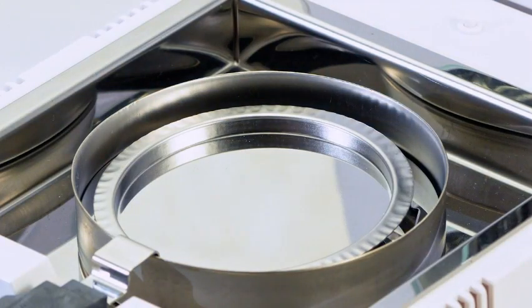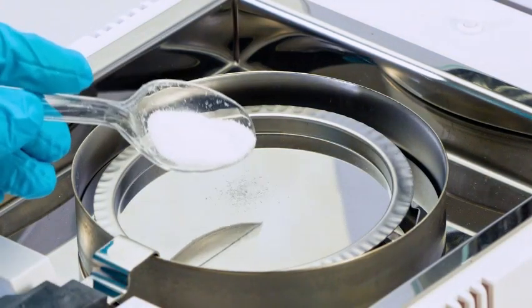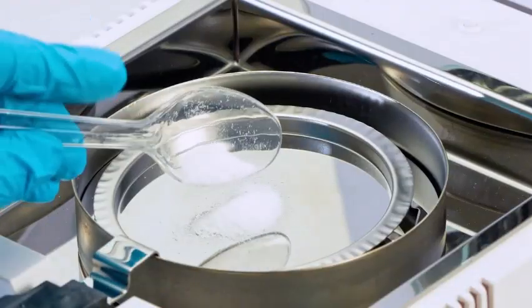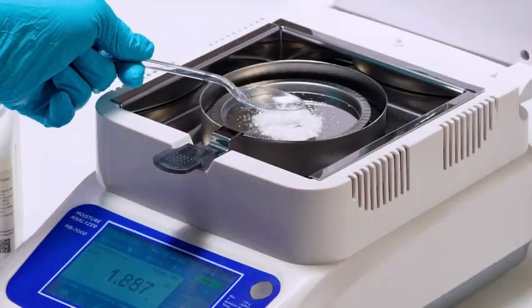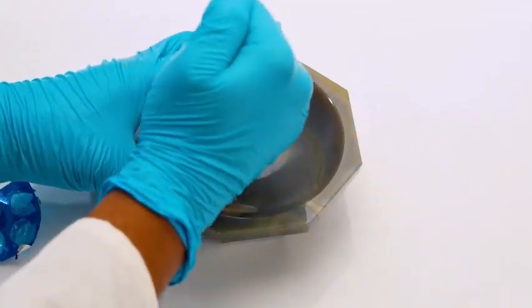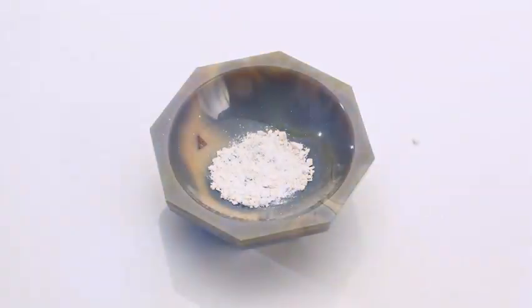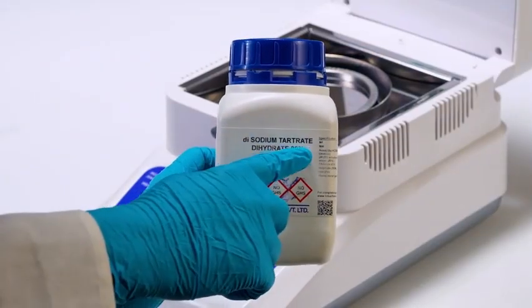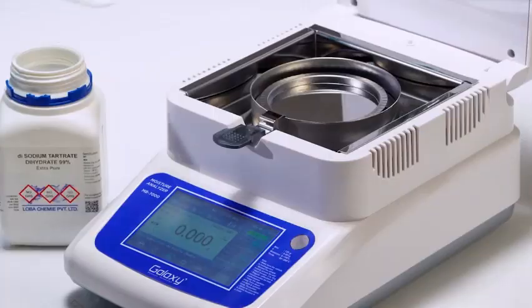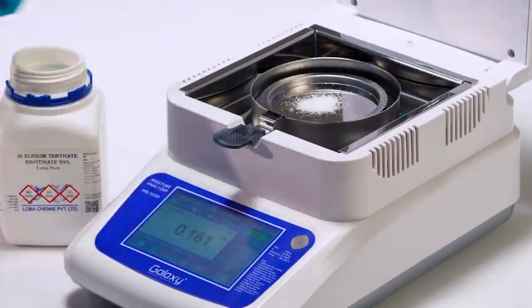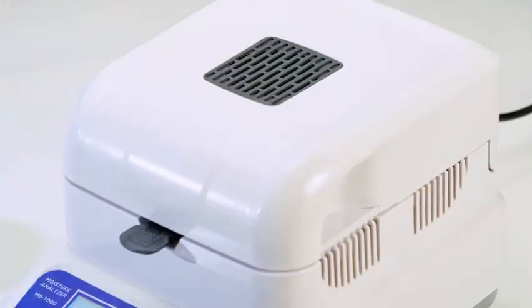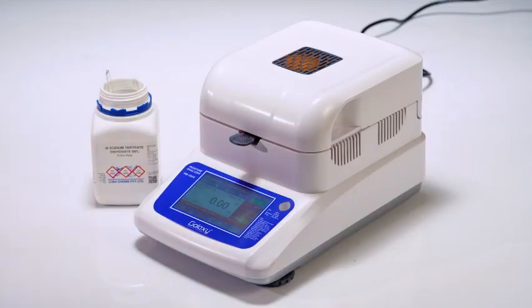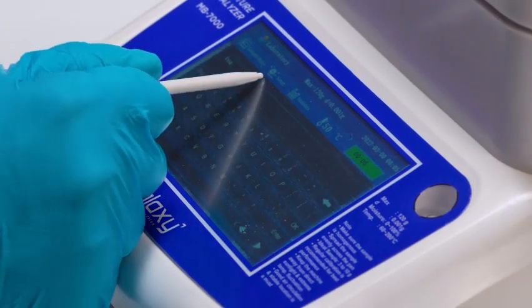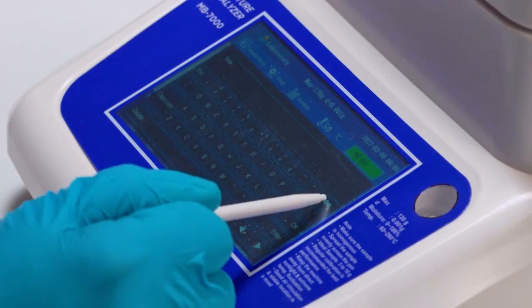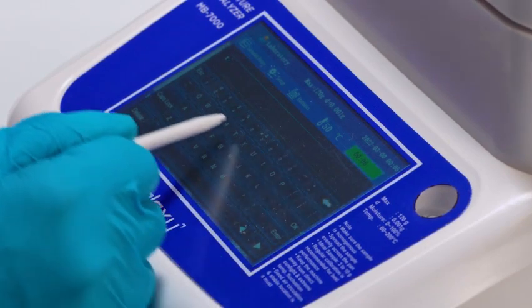How to take a moisture measurement? Let's first prepare our samples. For solids, spread powdery or grainy samples evenly on the dish. If the sample is coarse, grind it without generating heat to avoid moisture loss. We have taken our sample and spread it evenly on the pan. To update the sample name and ID, simply click on the option provided. Enter the new values, and you're all set. This ensures your sample information is accurate and up to date.